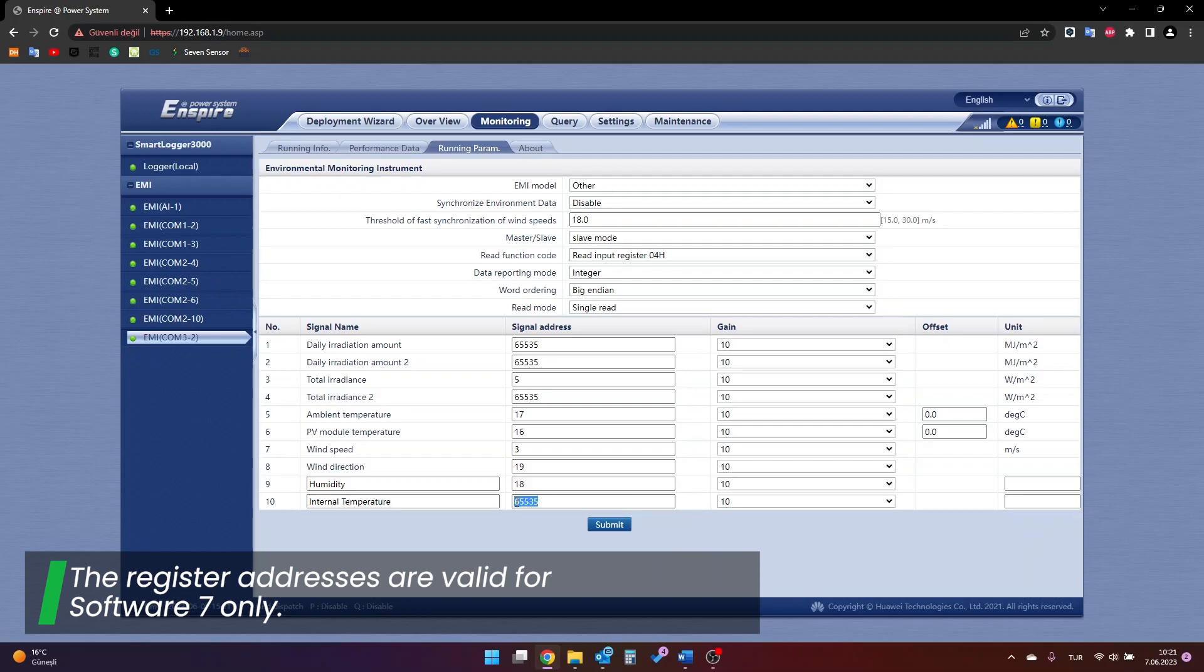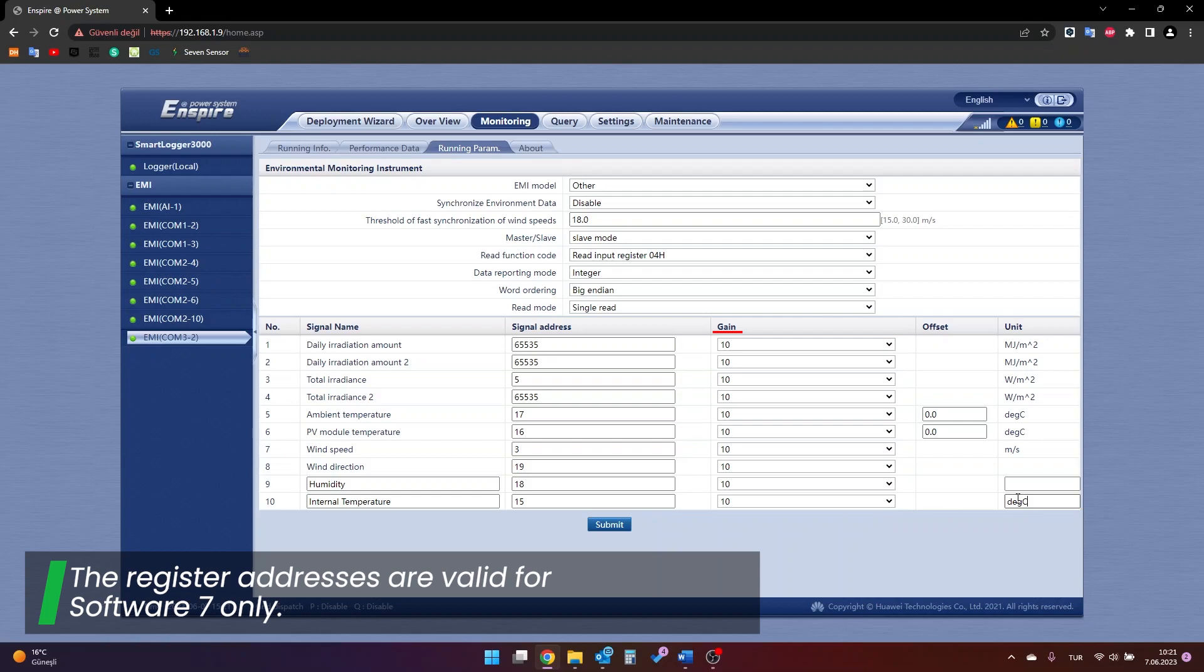After the register addresses are entered correctly, the coefficient selection process must be done correctly in the section specified as gain. The gain coefficient of the data whose registration address is entered is selected as 10. After all these are done, the saving process is performed with the submit option at the bottom.